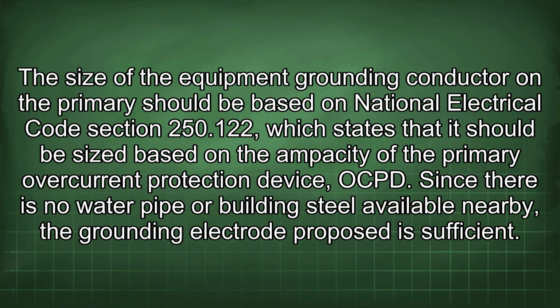250.66. The size of the equipment grounding conductor on the primary should be based on National Electrical Code Section 250.122, which states that it should be sized based on the ampacity of the primary overcurrent protection device, OCPD. Since there is no water pipe or building steel available nearby, the grounding electrode proposed is sufficient.